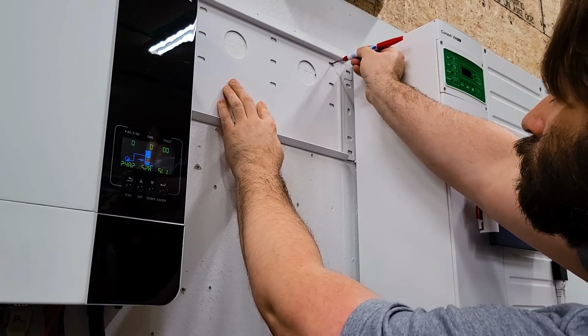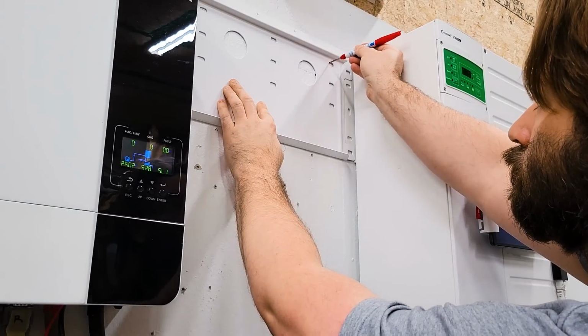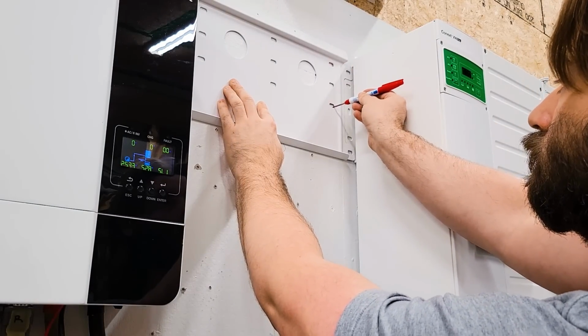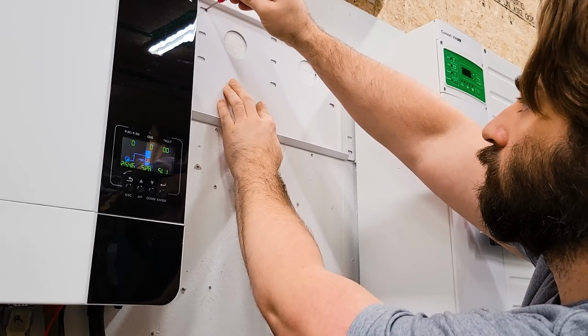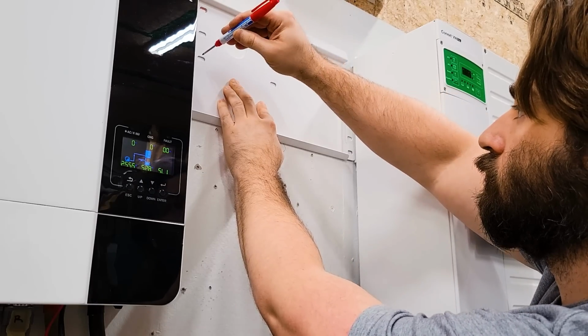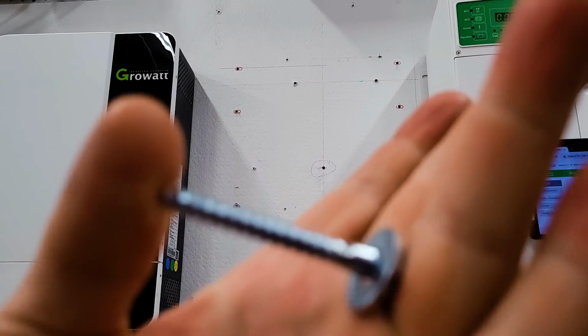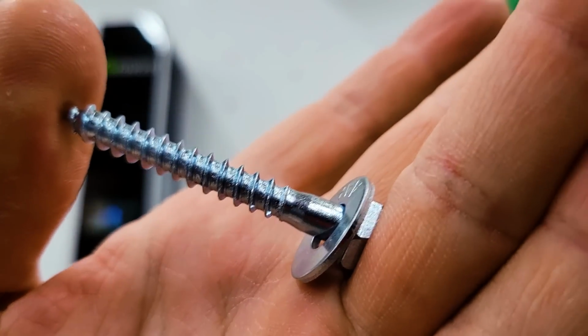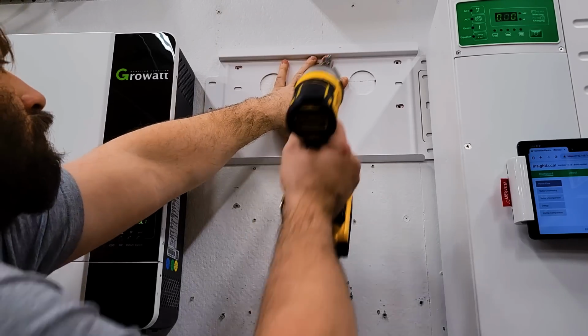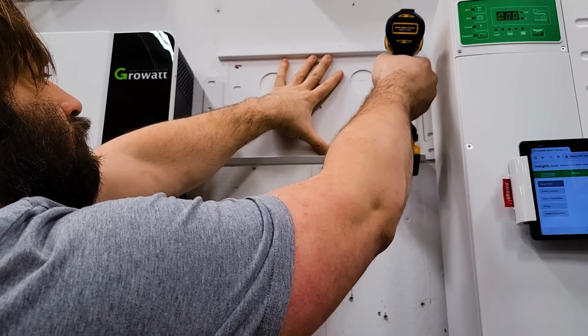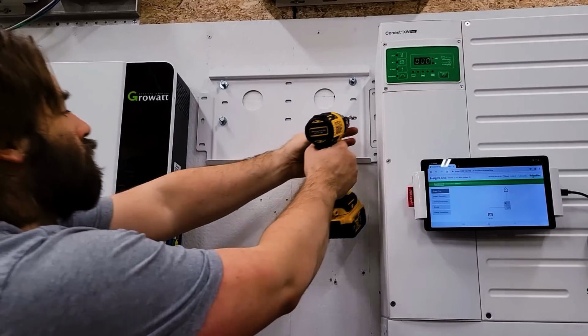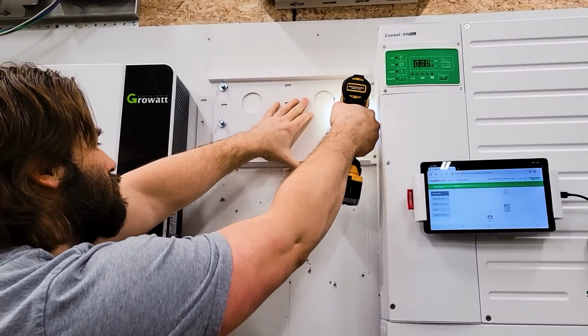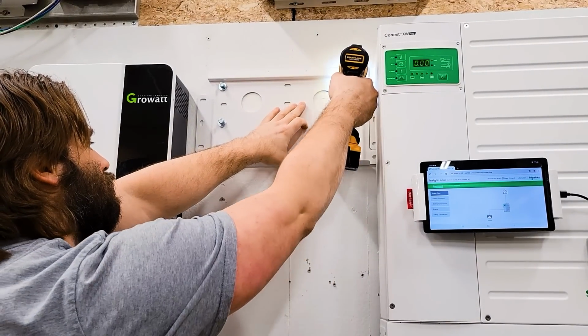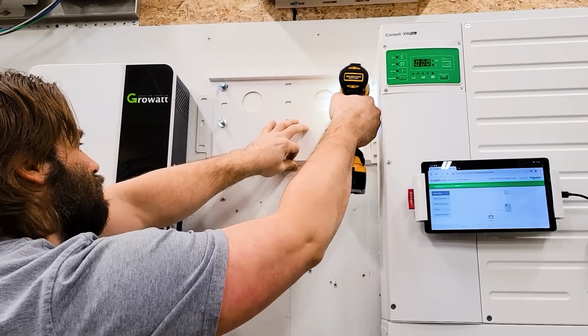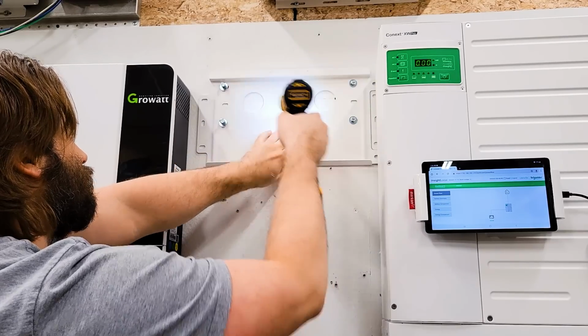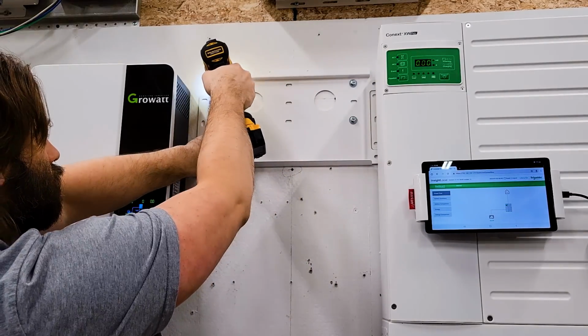The inverter comes with a steel wall hanging bracket that you screw to the wall. And it actually locks in with the one next to it, so they'll be in line with each other, and they can share support on a single stud. If you have studs 16 inches on center, the backing plates work out perfectly. My studs happen to be 24 inches on center, so I threw in a few extra 1/4 inch hardware. I used 1/4 inch lag screws and flat washers, and I screwed it through the cement backing board into the OSB and where I could into the stud behind it.